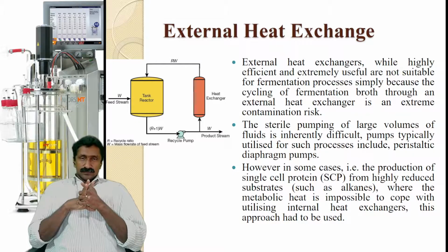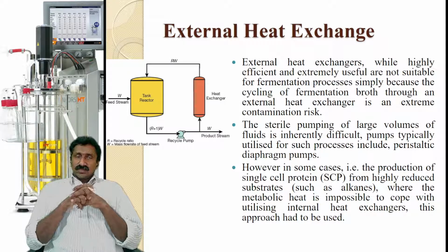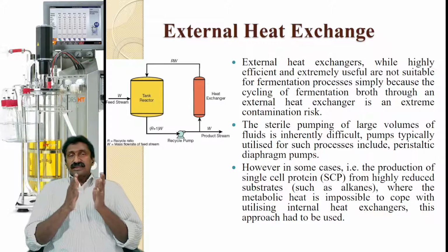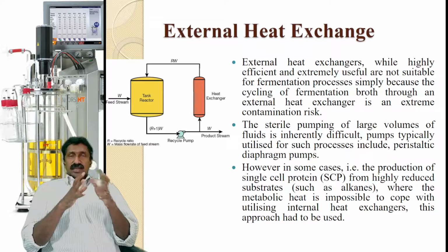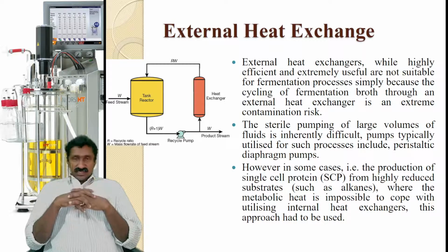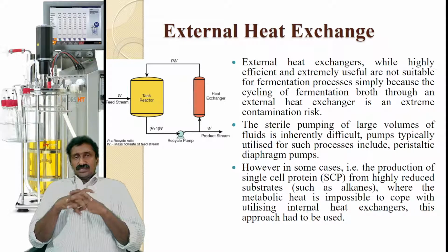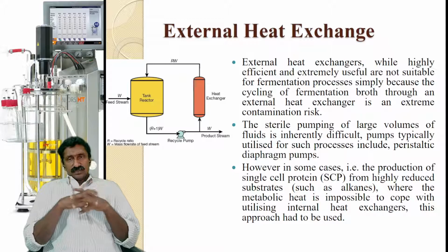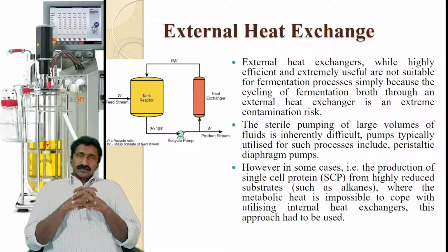Yes, sir. Okay. However, in some cases, that is the production of single cell protein, etc., from highly reduced substrates such as alkanes, where the metabolic heat is impossible to cope with utilizing internal heat exchangers or, say, jackets, then these types of external heat exchangers are required. Normally, it is not adopted because of the contamination risk, but in some cases where extra high heat generation is expected, like single cell protein production, you need to use such external heat exchangers.